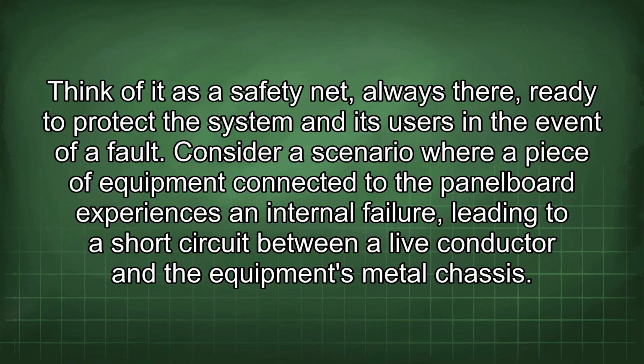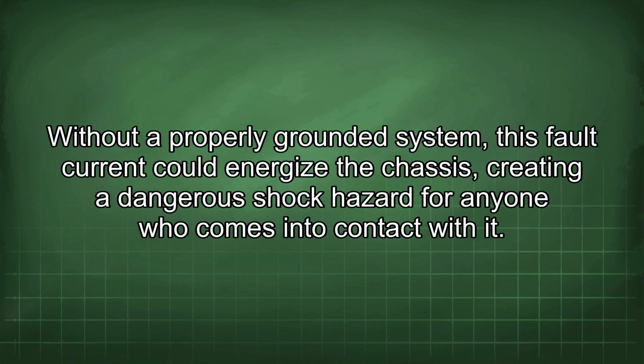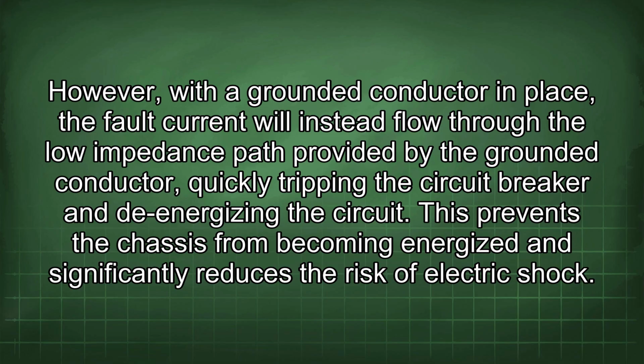Consider a scenario where a piece of equipment connected to the panel board experiences an internal failure, leading to a short circuit between a live conductor and the equipment's metal chassis. Without a properly grounded system, this fault current could energize the chassis, creating a dangerous shock hazard for anyone who comes into contact with it. However, with a grounded conductor in place, the fault current will instead flow through the low impedance path provided by the grounded conductor, quickly tripping the circuit breaker and de-energizing the circuit. This prevents the chassis from becoming energized and significantly reduces the risk of electric shock.